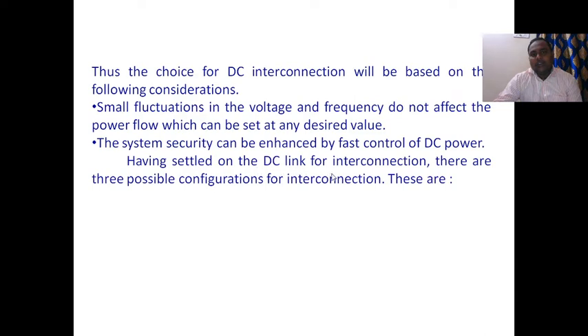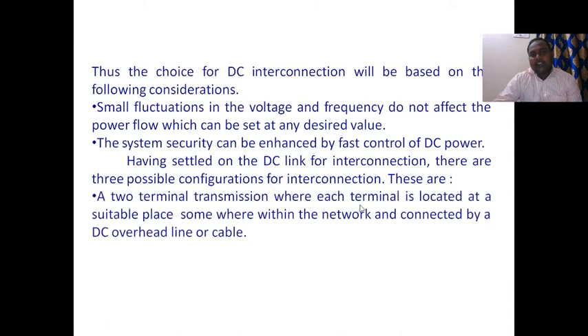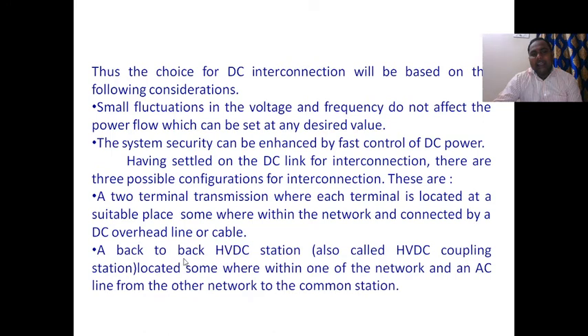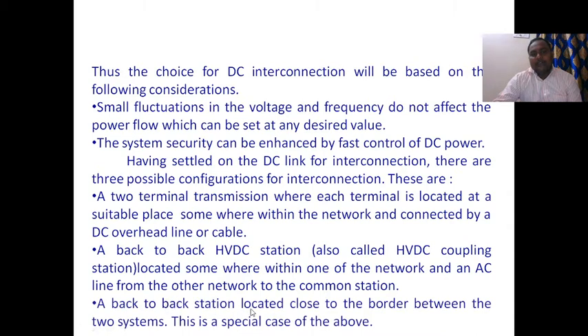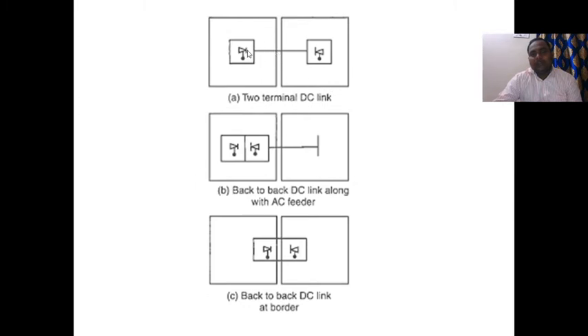Having settled on the DC link for interconnection, there are three possible configurations for the interconnections. A two-terminal transmission where each terminal is located at a suitable place somewhere within the network and connected by a DC overhead line or cable. A back-to-back HVDC station, also called HVDC coupling station, located somewhere within one of the networks and an AC line from the other network to the common station. A back-to-back station located close to the border between the two systems. This is a special case of the above. So this is a two-terminal DC link: converter 1, converter 2, and in between we use HVDC links.